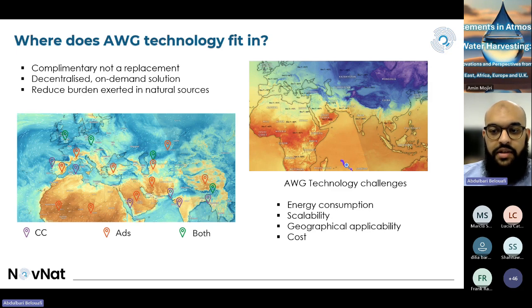Thirdly, another critical factor is geographical applicability. Relative humidity tends to be the metric used, but this only gives part of the story. What matters is the amount of water in the air, known as absolute humidity. In this regard, adsorption tends to be better than cooling condensation in drier regions, typically relative humidities below 50%, while cooling condensation is best suited to areas where relative humidity and temperature are high, which tends to be near coastal regions. In the image on the left, you can see a plot of where cooling condensation is better suited, where adsorption is better, and where both can be used. The issue is that cooling condensation, as I said, is restricted to coastal regions.